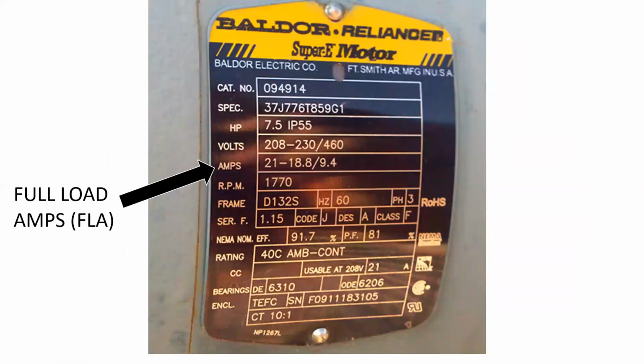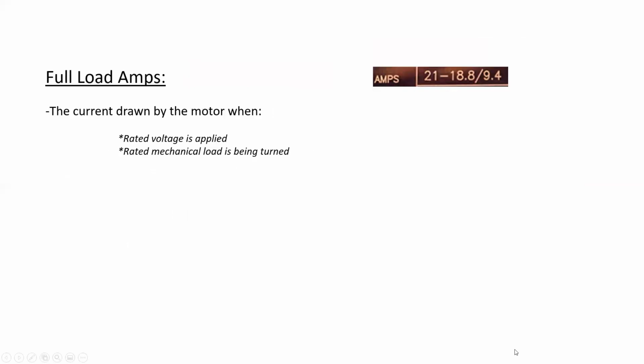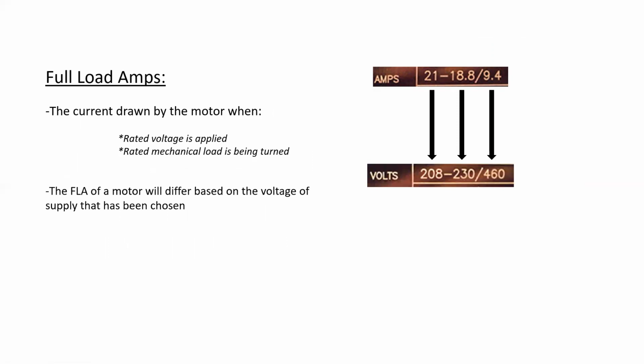Full load amps, or FLA. This one is 21 to 18.8 / 9.4 amps. The full load amps is the current drawn by the motor when rated voltage is applied and rated mechanical load is being turned. The FLA of the motor will differ based on the voltage of supply that has been chosen. And so you can see if we chose to connect this motor to a 208 volt 3-phase source, if it's driving its rated load, it'll draw approximately 21 amps. If instead we connect it to 230, it'll draw 18.8 amps. And if we connected it for the 460 volt range, we would draw 9.4 amps.